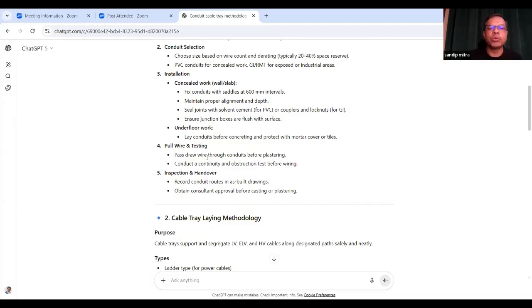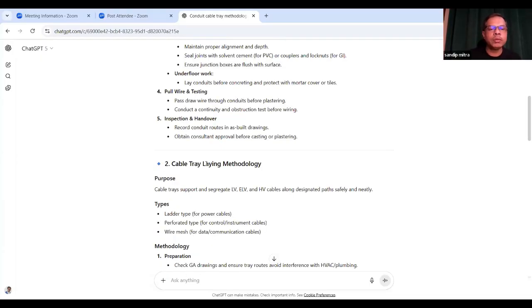You have to pass a draw wire through the conduit before plastering, because you have to check whether the conduit is choked or free flowing throughout. Sometimes concrete will come inside, so it may choke the conduit. At a later stage, it will be very difficult to pull wires through a choked conduit. So immediately you have to provide the GI wire or something. Then inspection and handover.